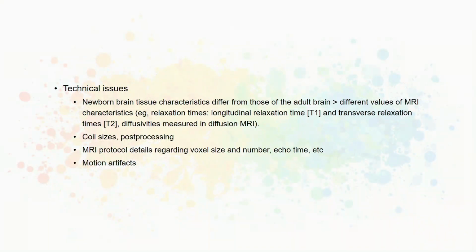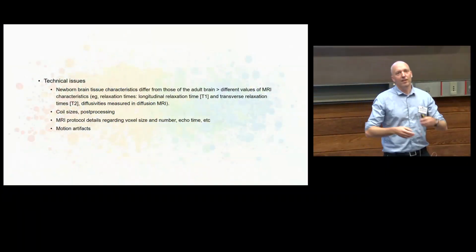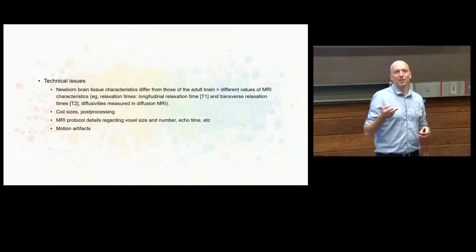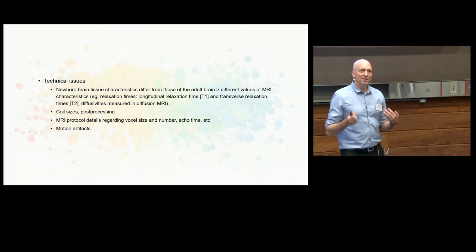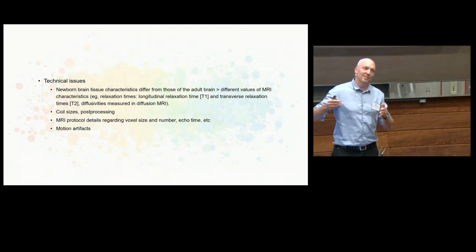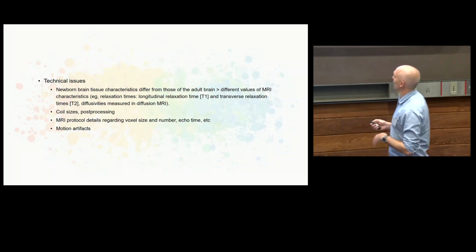And it turned out that, and it was really difficult to delineate, but our MRI people had a long chat with Siemens in Germany, and it turned out that the coil size relative to the piglet, there was some software that needed to be corrected, and then suddenly the results were flipped around. So I think you always need to pay attention, and there are so many steps that can affect your data, and it becomes a little bit of a trust as well.